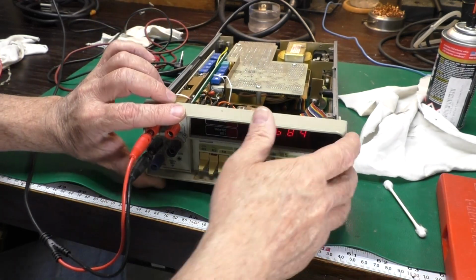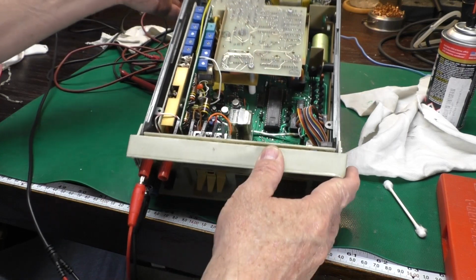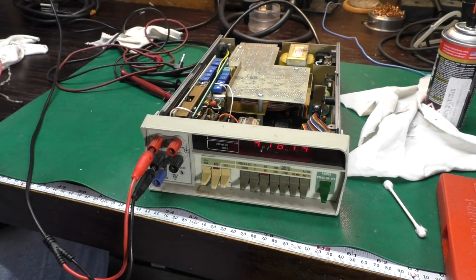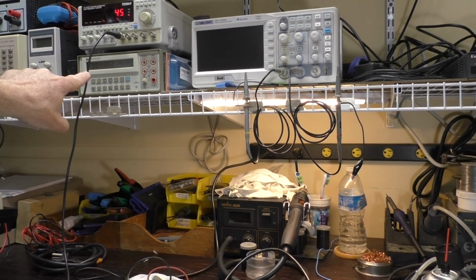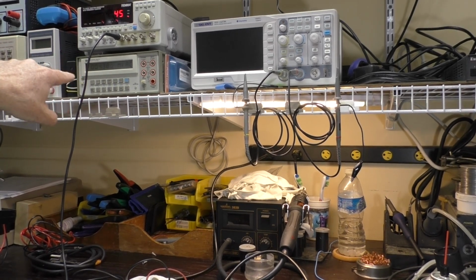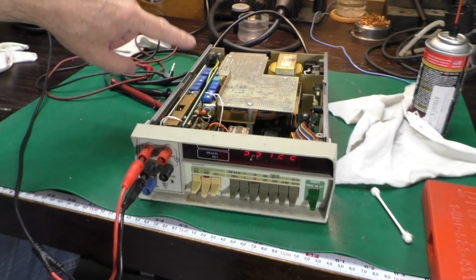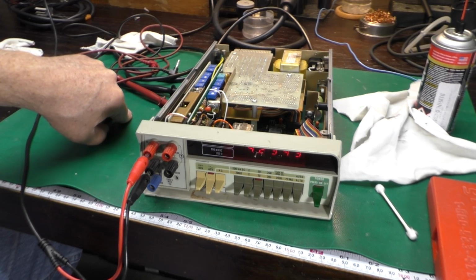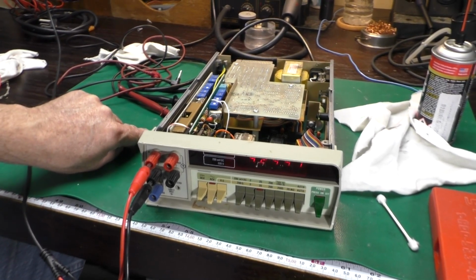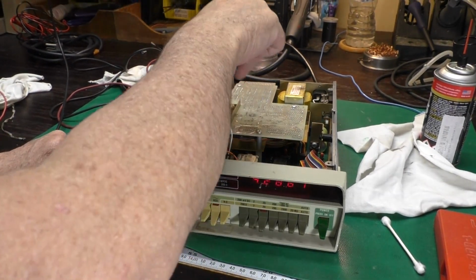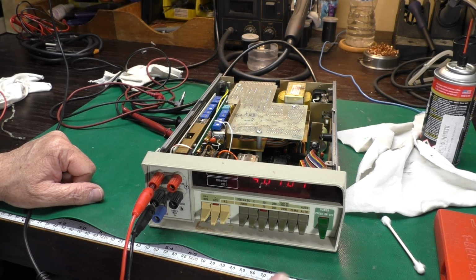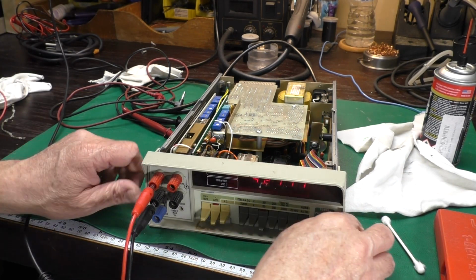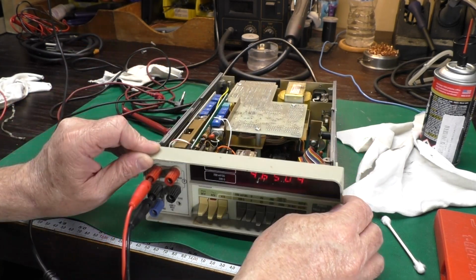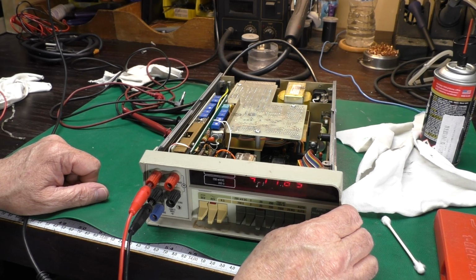Now, the difference between the calibration on this meter, which has all the pots here on it, and the HP right here, is that the HP is all electronic calibration. It stores the calibration values in a non-volatile RAM chip, whereas this one, it's all a bunch of pots, and you've got to go through a very specific procedure and tweak every one of those pots. So either way, the electronic or mechanically tweaking the pots can take a while to get it dialed in right, and you've got to leave the calibration machine on for hours first so it gets warmed up inside. Leave this on for hours, in a relatively temperature controlled environment so you can set it. So I'm going to go ahead and clean the sticky off this lens if I can and get this thing buttoned back up, and we'll have a look at the Fluke 8000s.